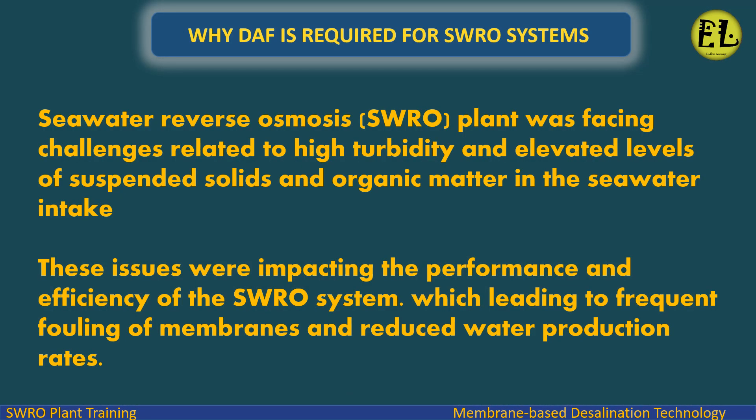A Seawater Reverse Osmosis (SWRO) plant was facing challenges related to high turbidity and elevated levels of suspended solids and organic matter in the seawater intake. These issues were impacting the performance and efficiency of the SWRO system, leading to frequent fouling of membranes and reduced water production rates.